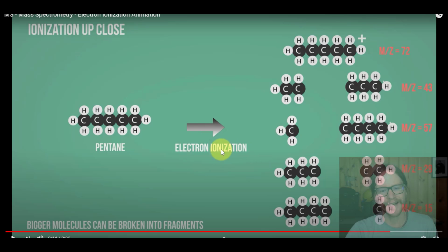molecules is that as long as our electron ionization step is consistent, meaning as long as we're applying the same energy into our electron ionization step, which is standard, typically 70 electron volts, then what we get is a pattern of abundances of various fragments of the original molecule that's unfragmented. And from this, we can deduce what the original molecule was, and we can compare across systems, because as long as everybody is smashing apart their molecules in the same way, they get nominally the same pattern. And so this is generally how electron ionization will occur.